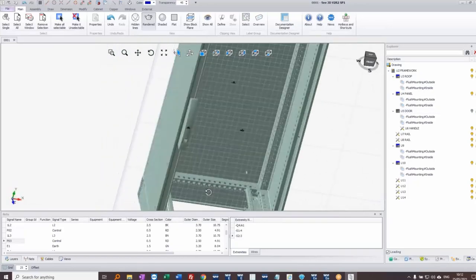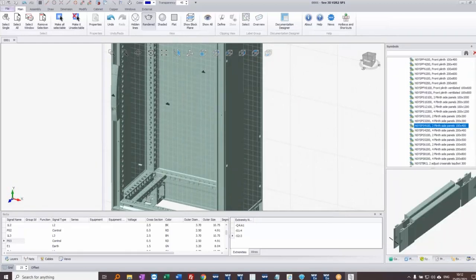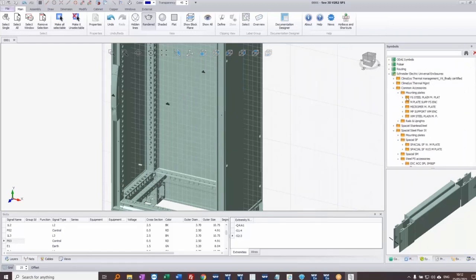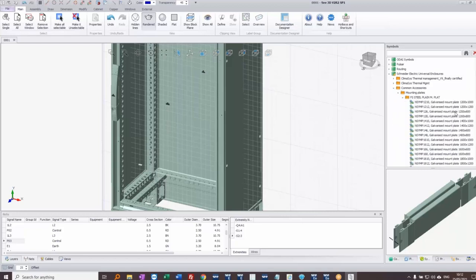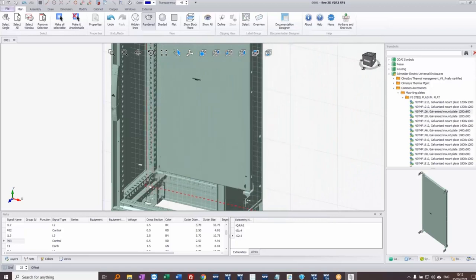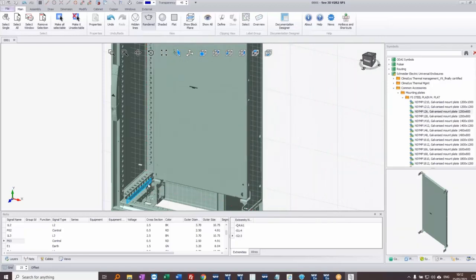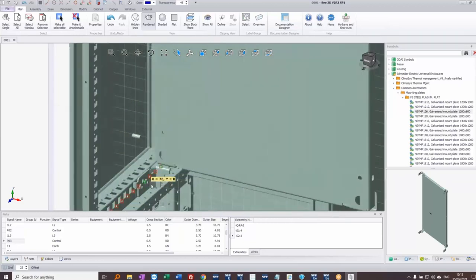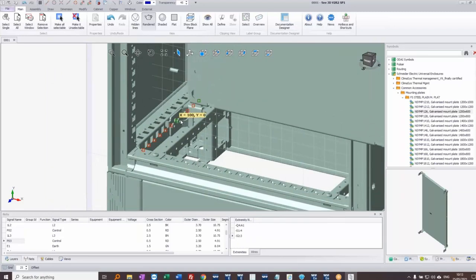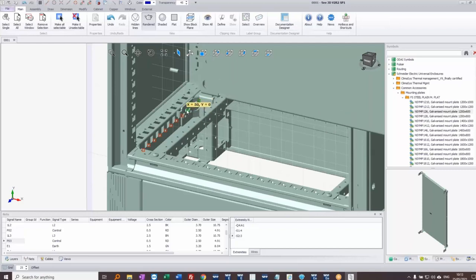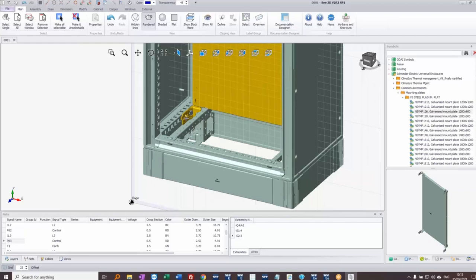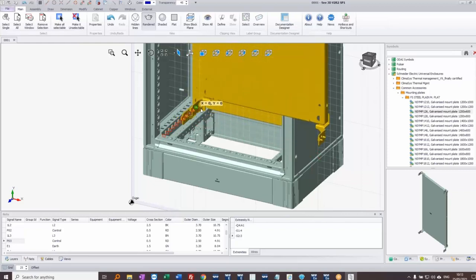Since there's no mounting plate yet, I have an empty chassis. I'll go back to symbols, navigate to common accessories and mounting plates, and select a steel mounting plate at 1200 by 600. I hold it in the bottom-left and notice the mounting planes highlighted in blue. I can click to place it, and use snap points to position it at different depths in 25mm grid increments — all the way to the back or stepped forward. I double-click and choose to position it right at the back.